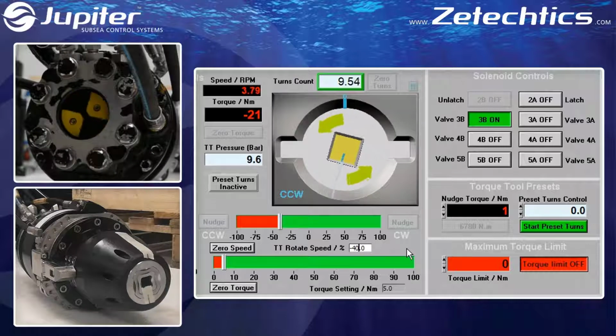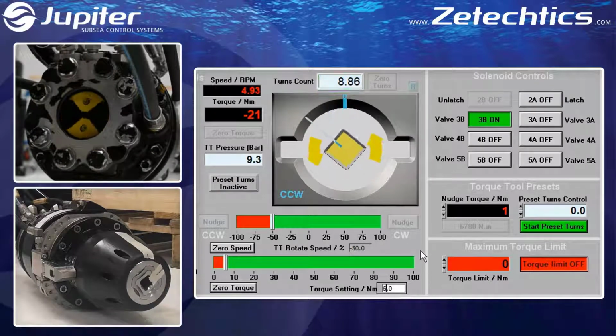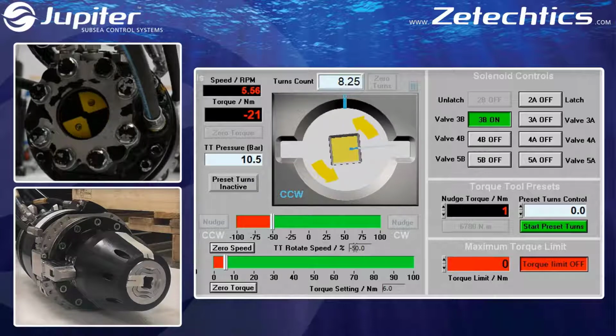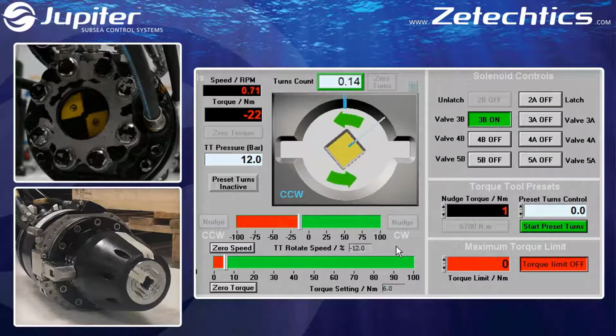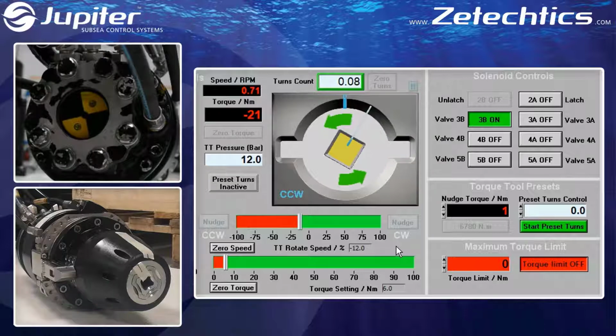Steadily increase the flow to prove proportional control. The tool should be capable of 5 RPM in high gear. Continue running the tool until 10 turns have been completed. Ensure the turns feedback matches the number of turns performed. This will be -10 if starting from 0.